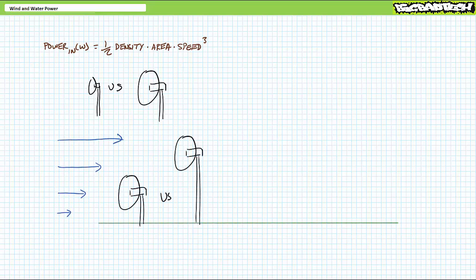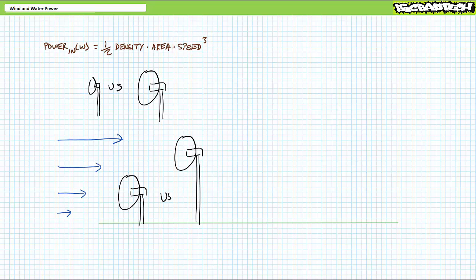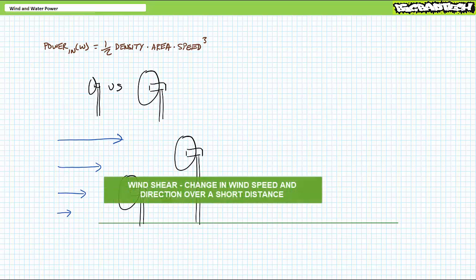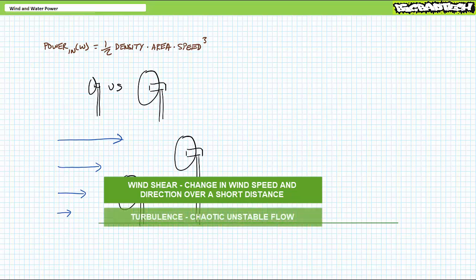Why are they so tall? The wind power input formula demonstrates that higher wind speeds yield substantially more input. Horizontal axis wind turbine generators place the rotor on a tower well above the slow-moving air at the surface and immerse it inside a region of unobstructed flow. At the surface, there exists wind shear, which is a change in wind speed and direction over a short distance, and turbulence, which is a chaotic, unstable flow.